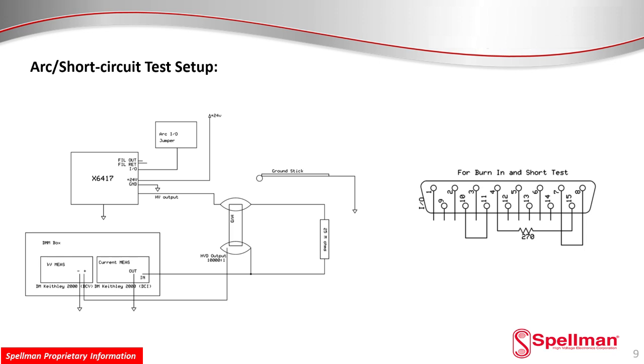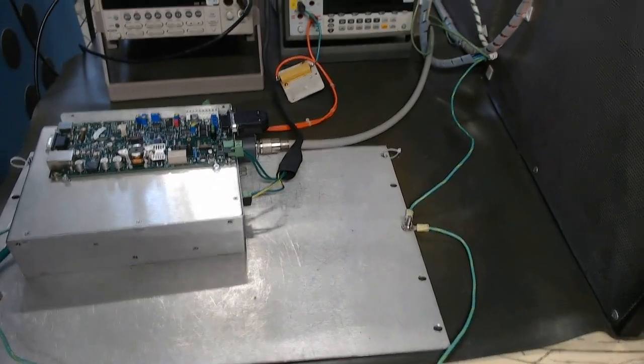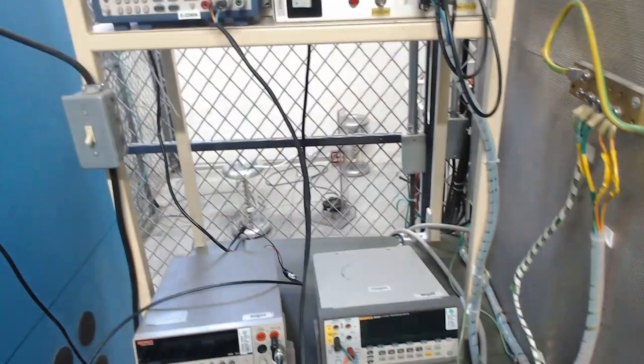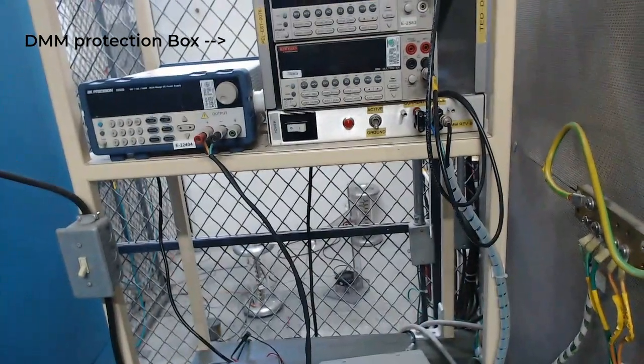Final test begins with the arc testing, and the configuration is the one shown in the video. It can be observed that the generator is disconnected from a majority of the measurement equipment with the exception of the DMM protection box, which is intended to protect the equipment during an arcing event. A ground stick is used to short-circuit the output directly while the generator provides full rated output. As shown in the test demonstration, you can notice equipment is disconnected from the X6417, with the exception of the ones in the DMM box.